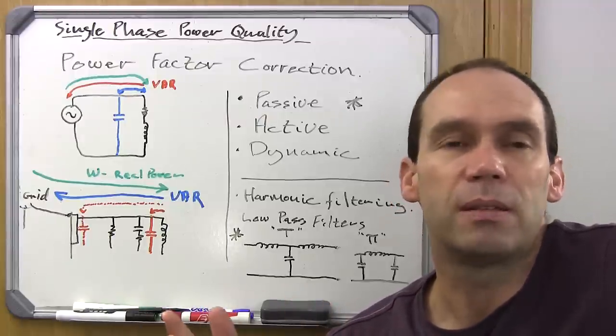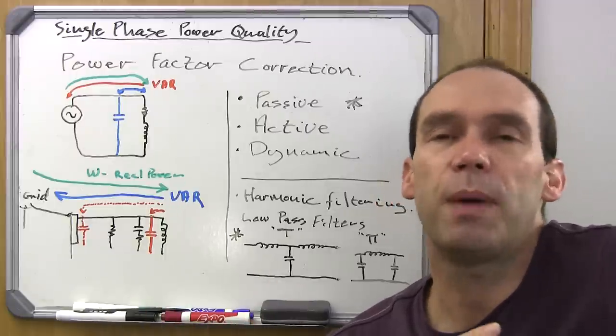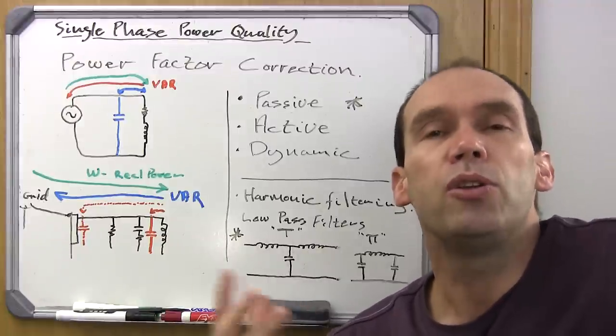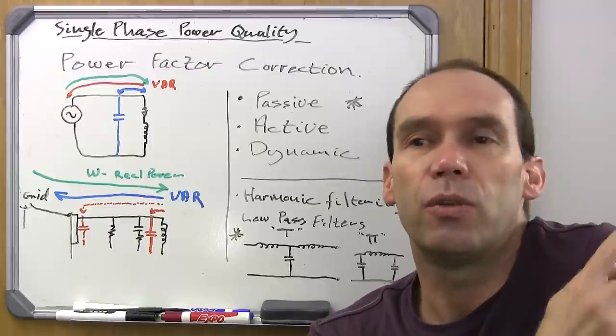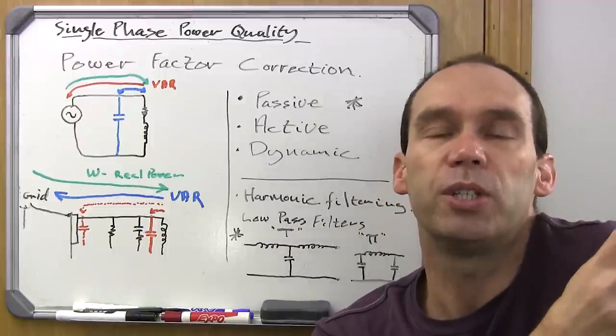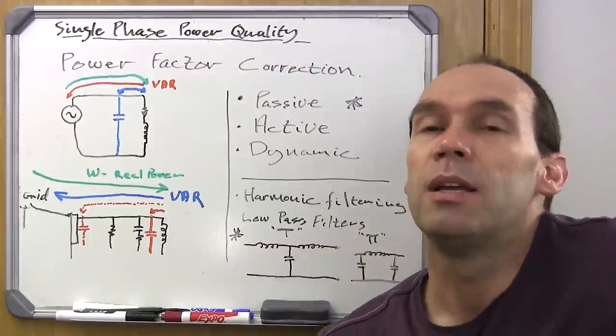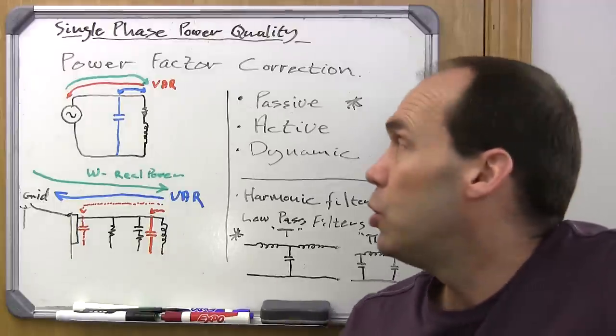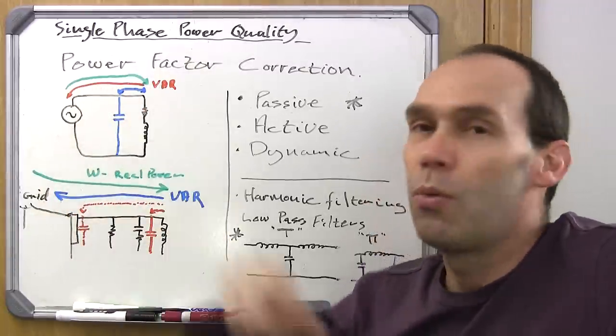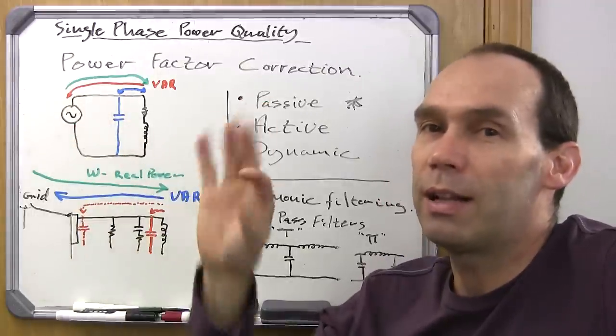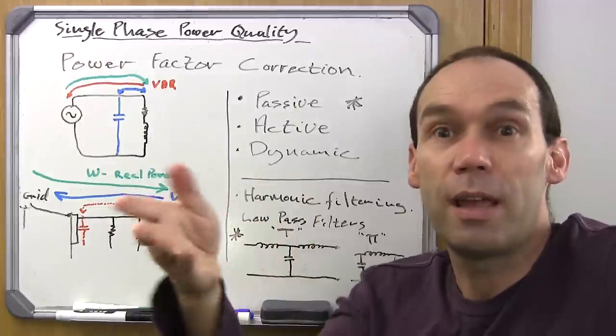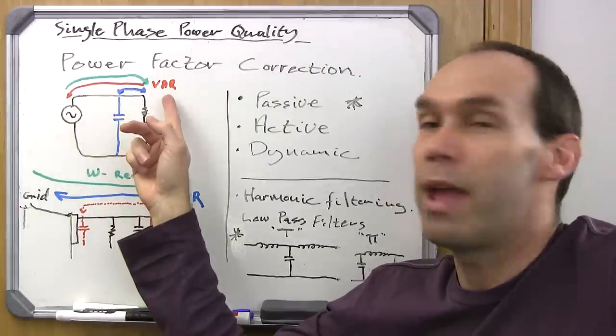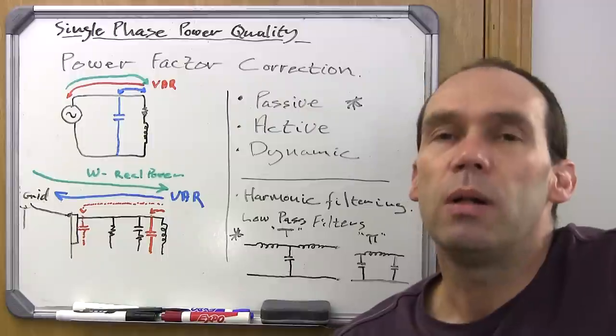Power factor issues at residences may just be too small to be worth pursuing. We do send reactive power back onto the grid, and if you implement power factor correction at home and it works, you are doing a good thing by not pushing excess reactive power onto the grid. But you won't save any money doing that. Don't be caught by the snake oil of these companies. They demonstrate on YouTube how, without their device, you have more current on the line; they plug the device in, the current drops, and claim you're saving money. Those amps they're saving are reactive power — which you're not being charged for.